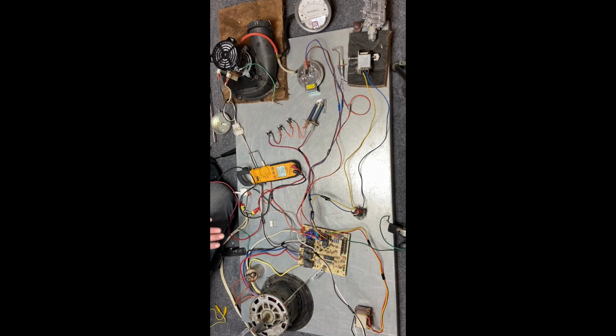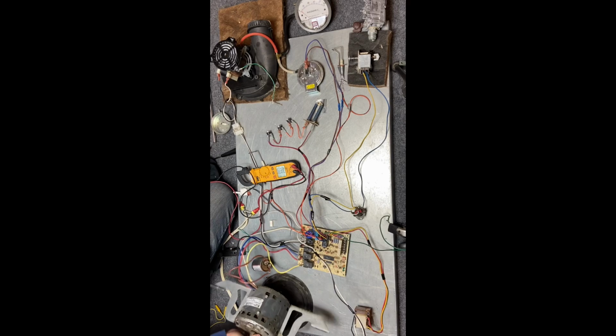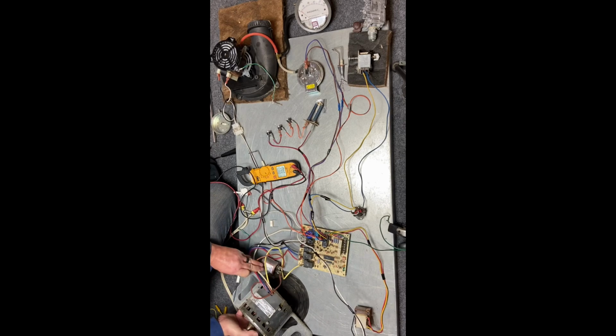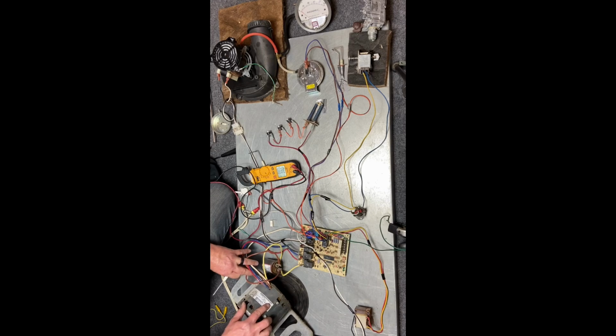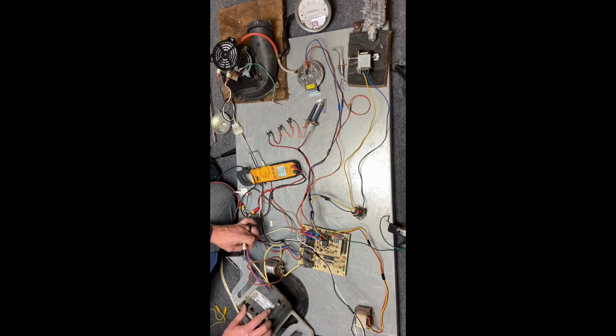Now you saw me check amperage to see do we have a flow of electricity. But there's another thing we want to do with that amps. I want to check the amps of this motor and compare it to the tag of the motor. These motors are going to have a rating set for it. And this motor tells us the rotation, the horsepower, and right over here it has the amp rating, 7.10 amps. I want to make sure I'm not overamping this motor. So if I'm checking the amps of the motor, I want to make sure I'm below that number.